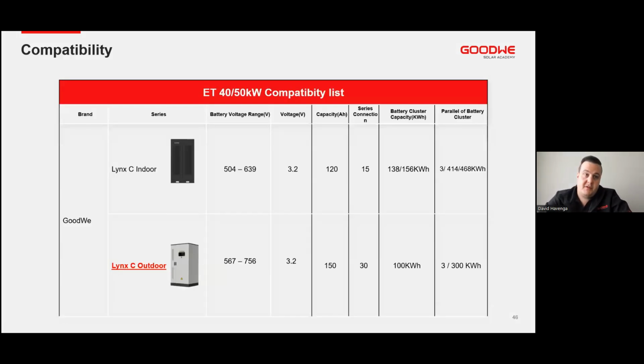Looking at our compatible batteries from GoodWe, we have our Lynx C Indoor. The Lynx C Indoor does go from a smaller capacity all the way up to 156, but for the 50 kilowatt we recommend the 138 to 156 kilowatt hour battery. This is because these batteries are only 0.4C discharge, so use the 138 as the minimum for the 50 kilowatt. We can also parallel up to 3 batteries per inverter, so that can give you quite a large battery. That's where we can have the 414 or 468 kilowatt hours.